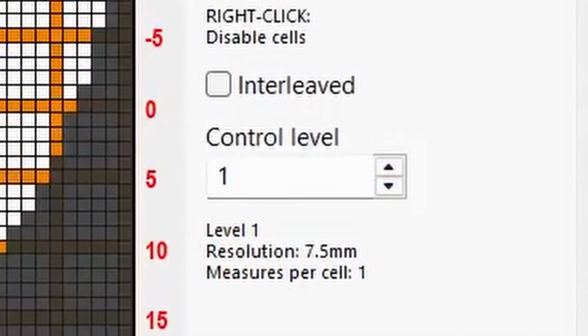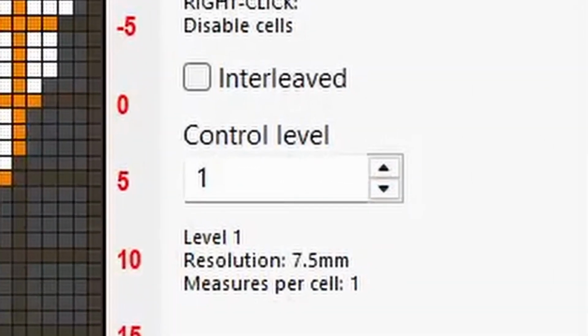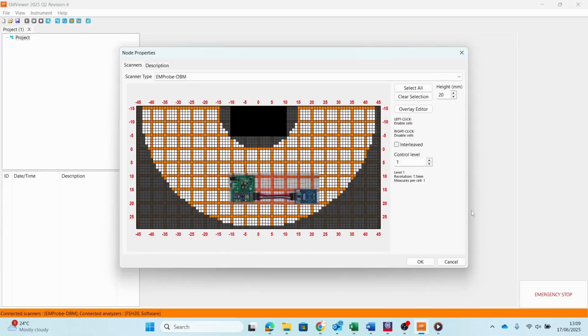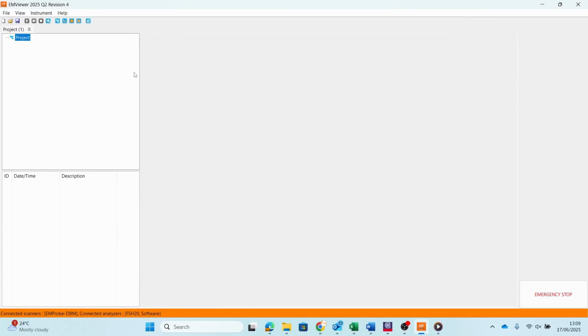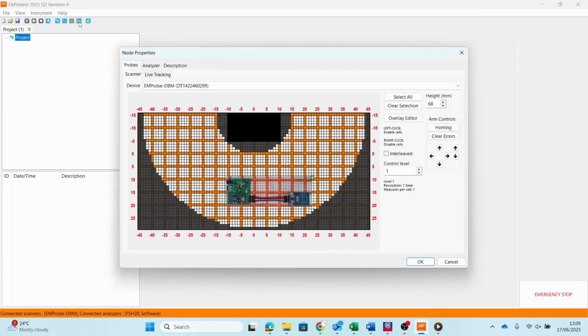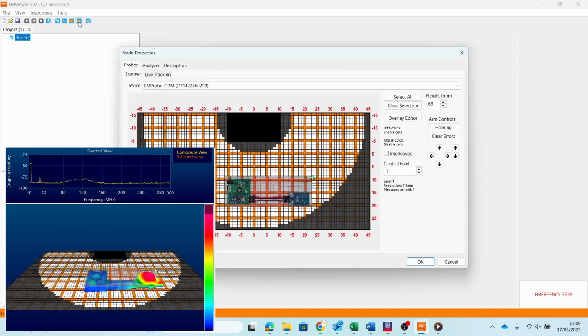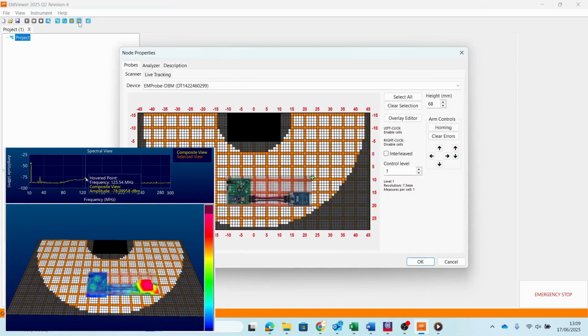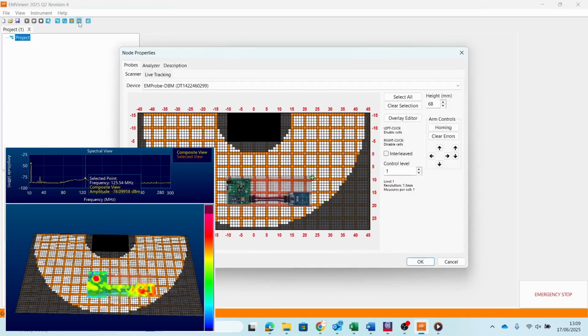The control level represents the resolution of the scan. For this scan, we will use level 1, which performs a single measurement per 7.5 mm cell. Now, we will select the mode of operation. In this case, we will use the combined mode, which provides us with the frequency response across the area, as well as a visualization of power measured from each cell.